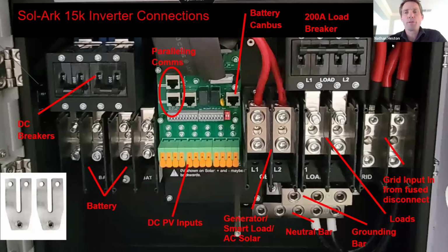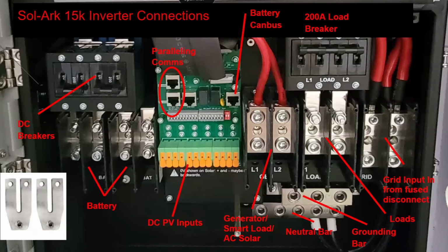Let's talk just a little bit about the wiring of a Sol-Ark 15K. Of course, you can find most of this in the manual, but I do want to highlight that if you only use one of these sets of breakers, so you've got 2 positives on the left, 2 negatives on the right, the Sol-Ark is going to limit your overall power. Is that correct, John? Yeah, that's correct. You'll see that they both have these 200 amp breakers on each input protecting it, and so you can't get 275 amps off of one port. You need both ports to get the full backup capability.